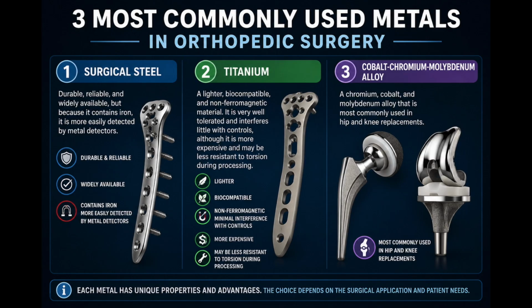The first is surgical steel, which is durable, reliable, and widely available, but because it contains iron, it is more easily detected by metal detectors. The second is titanium, a lighter, biocompatible, and non-ferromagnetic material. It is very well tolerated and interferes little with controls, although it is more expensive and may be less resistant to torsion during processing. The third type of metal we use is a chromium, cobalt, and molybdenum alloy that is most commonly used in hip and knee replacements.